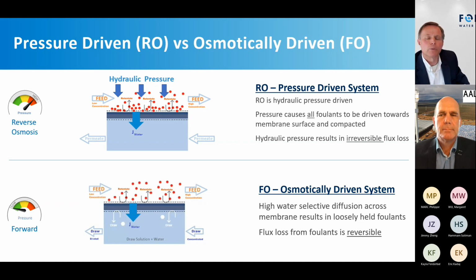With FO, remember, we're just drawing water across. It doesn't mean we're not going to foul the membranes, but when we do foul, it's a very loose matrix and very easy to clean. So much so that if I just push water across at a high velocity and scour it, that'll clean the membrane off and recover my flux without the use of chemicals. And on the environmental side, we want to minimize the amount of chemical use we have on site.